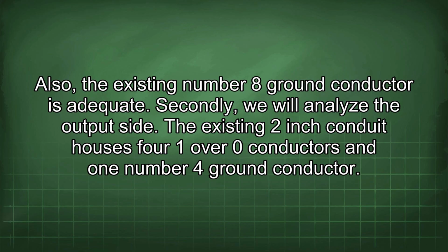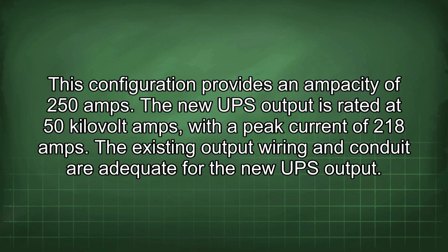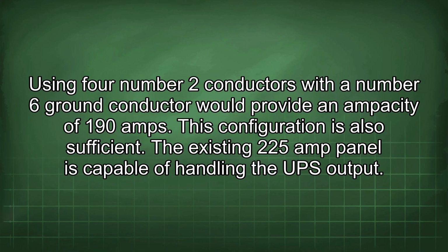Secondly, we will analyze the output side. The existing 2-inch conduit houses 4 1/0 conductors and 1 number 4 ground conductor. This configuration provides an ampacity of 250 amps. The new UPS output is rated at 50 kV amps with a peak current of 218 amps. The existing output wiring and conduit are adequate for a new UPS output. Using 4 number 2 conductors with a number 6 ground conductor would provide an ampacity of 190 amps. This configuration is also sufficient. The existing 225 amp panel is capable of handling the UPS output.